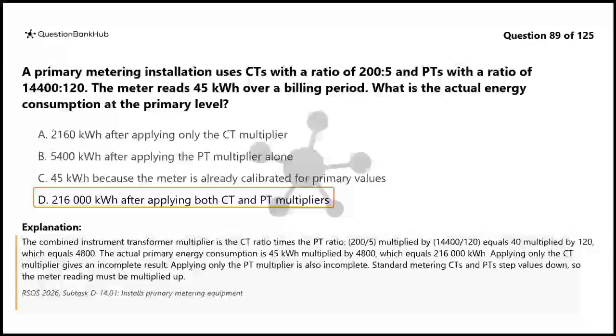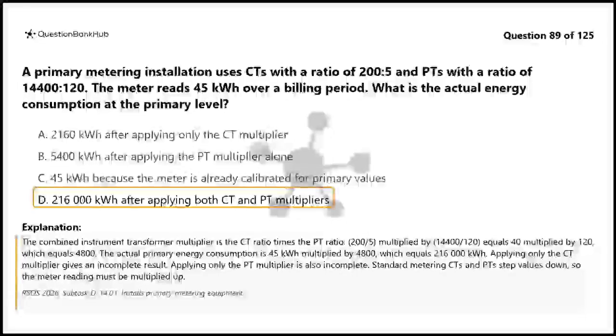The combined instrument transformer multiplier is the CT ratio times the PT ratio: 200/5, multiplied by 14,400 over 120, equals 40 multiplied by 120, which equals 4,800. The actual primary energy consumption is 45 kilowatt-hours multiplied by 4,800, which equals 216,000 kilowatt-hours. Applying only the CT multiplier gives an incomplete result. Applying only the PT multiplier is also incomplete. Standard metering CTs and PTs step values down, so the meter reading must be multiplied up.